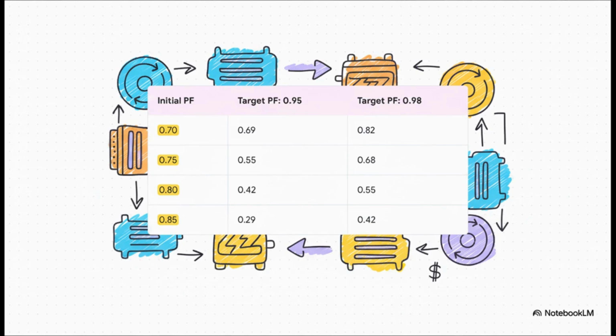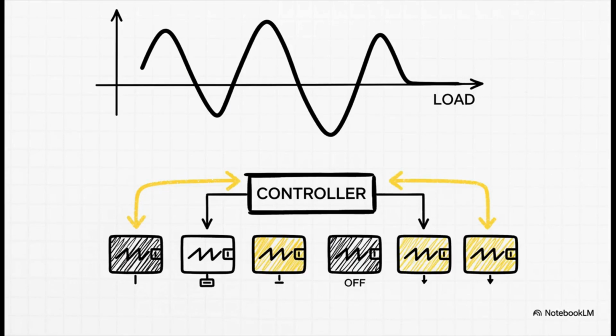Simple as that. But here's the thing, a factory's load isn't constant, right? It changes all day as shifts start and end and machines turn on and off. That's why you can't just install one giant capacitor and call it a day. That's where automatic controllers come in. Think of them like a smart thermostat for your power factor. They're constantly monitoring the system and switching smaller capacitor banks in and out step by step to perfectly match the real-time needs of the system. This also prevents a really dangerous overcorrection.